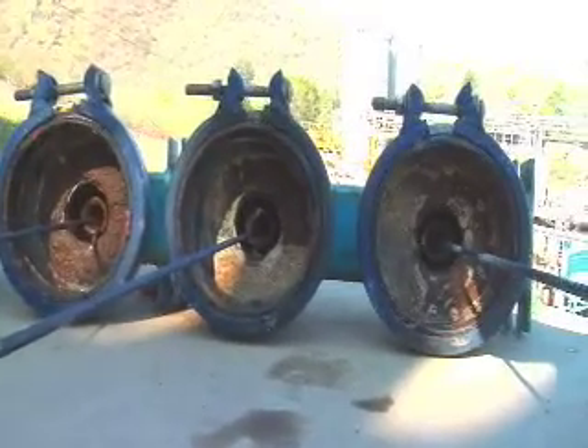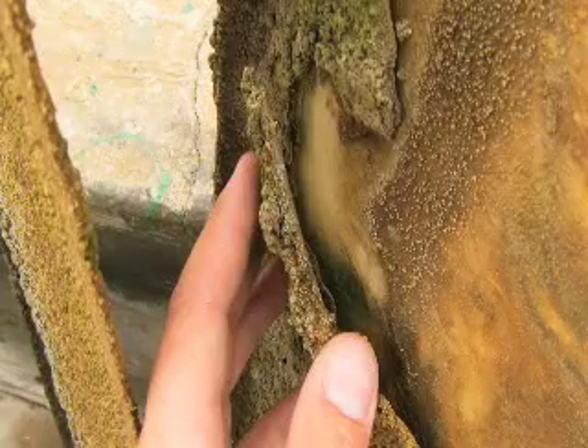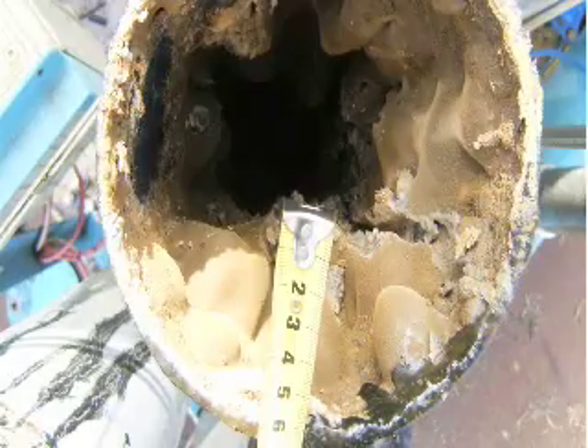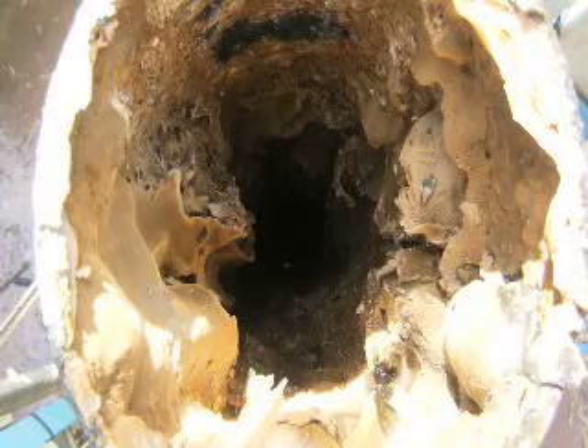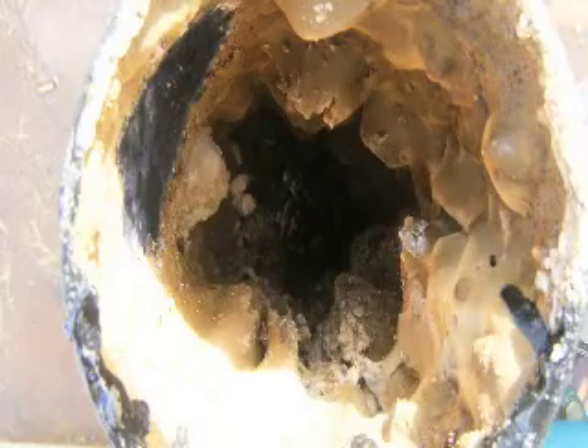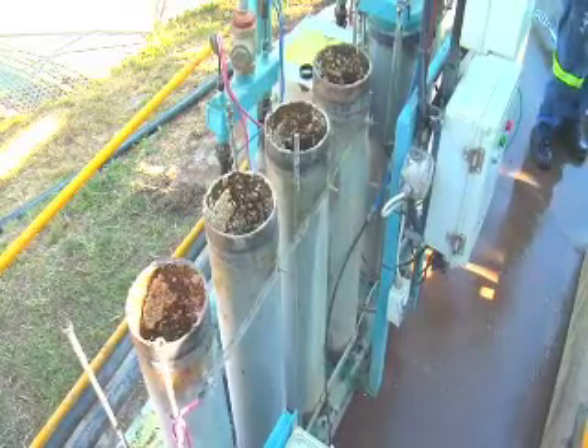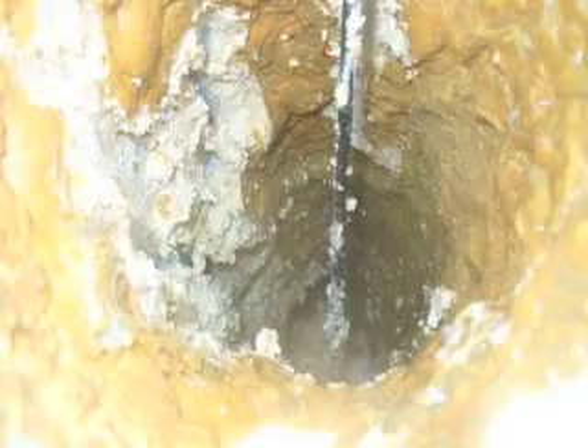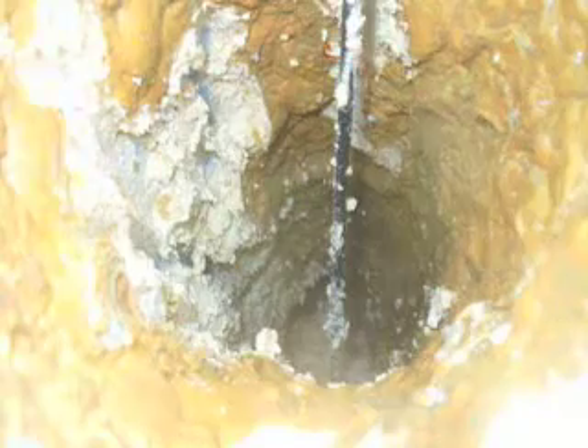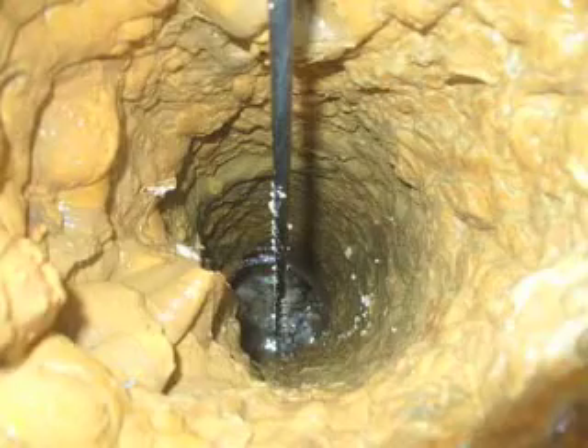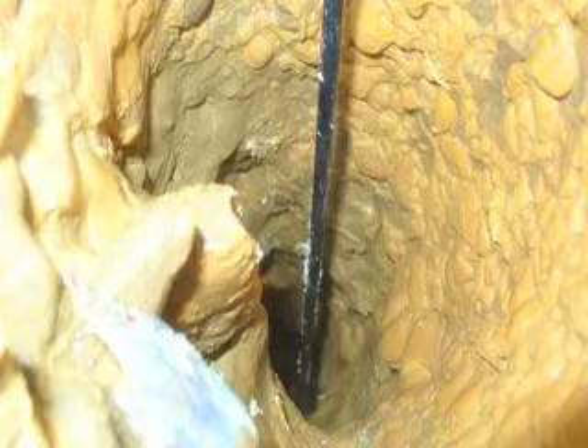Okay, the WESU system has been installed now for approximately a year. In the beginning we had a lot of scale formation in the reactor pipes. Also the color was more dark, so there were a lot of impurities. In the last 2-3 months we found that the amount of scaling has reduced dramatically. And the last color that we looked at, the scaling is more whitish calcium carbonate. So it shows you that it's mostly the calcium carbonate that comes from the fresh water.